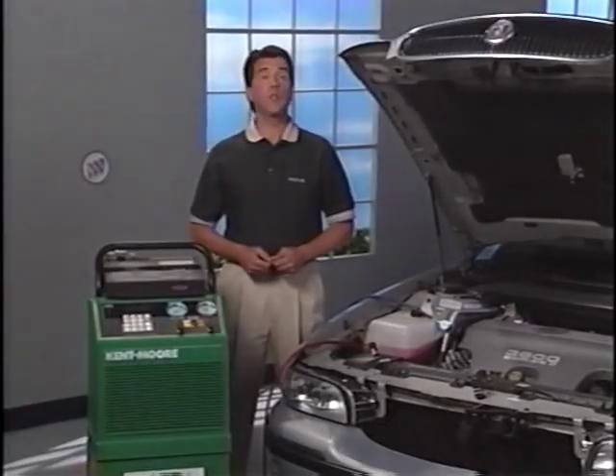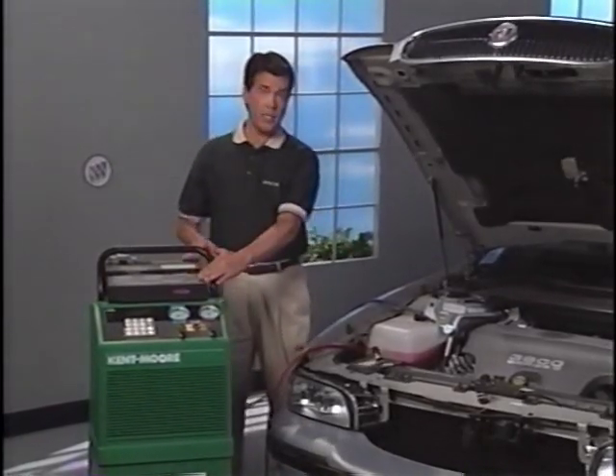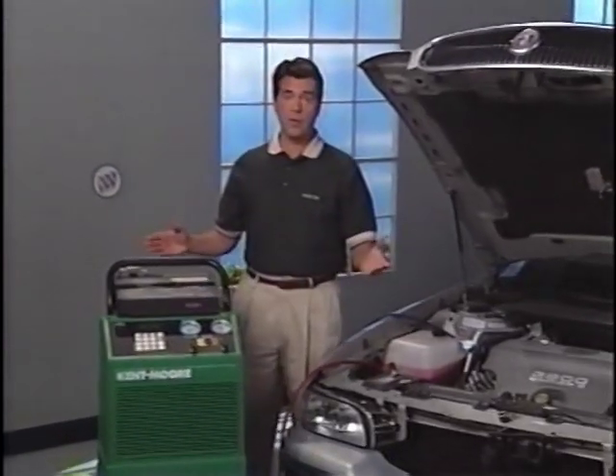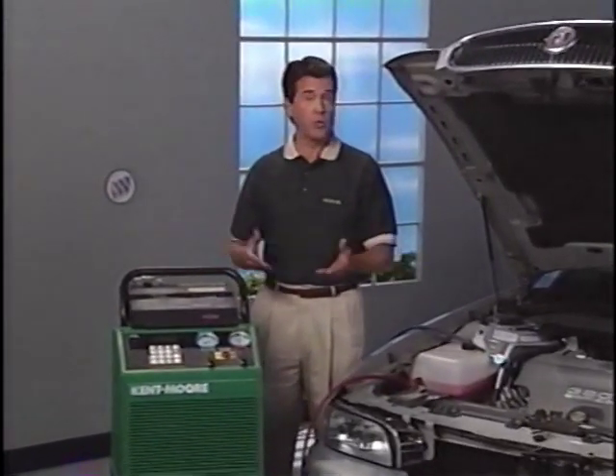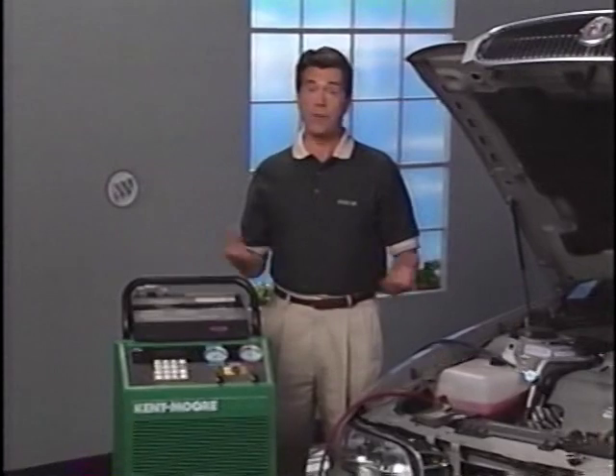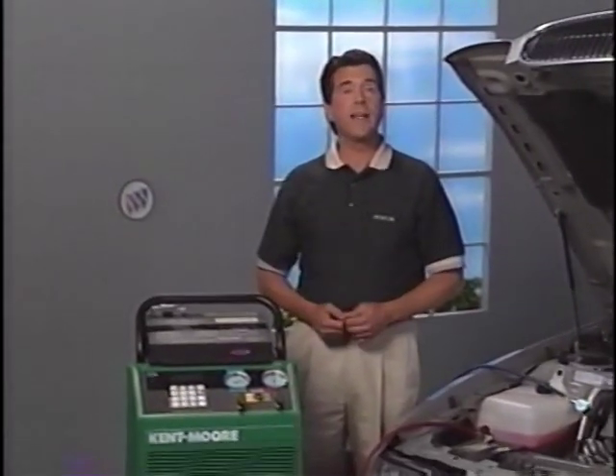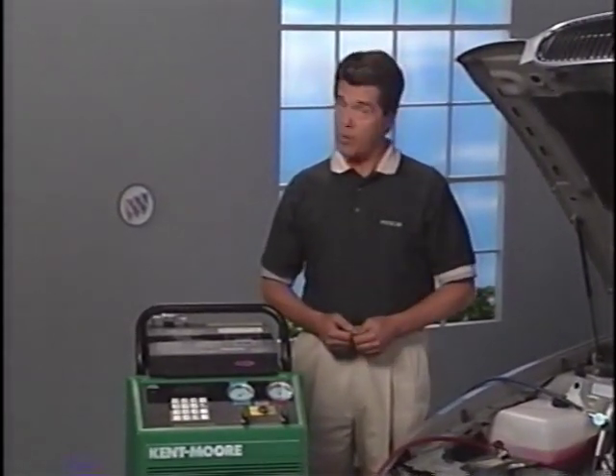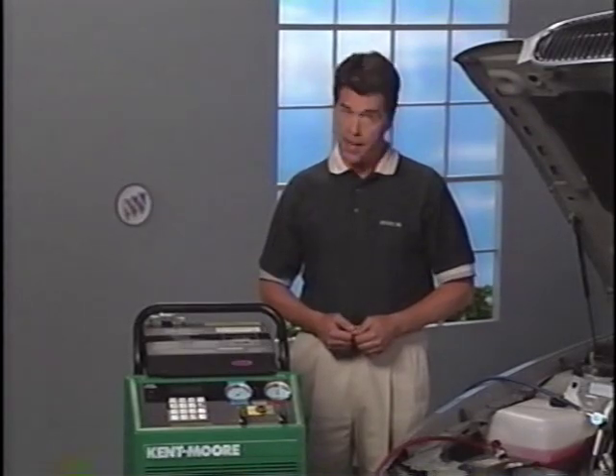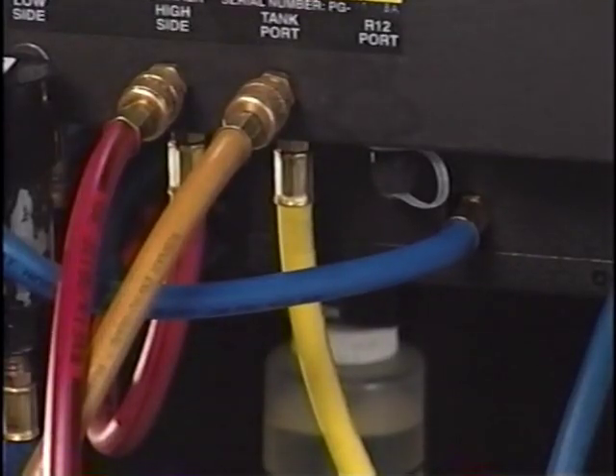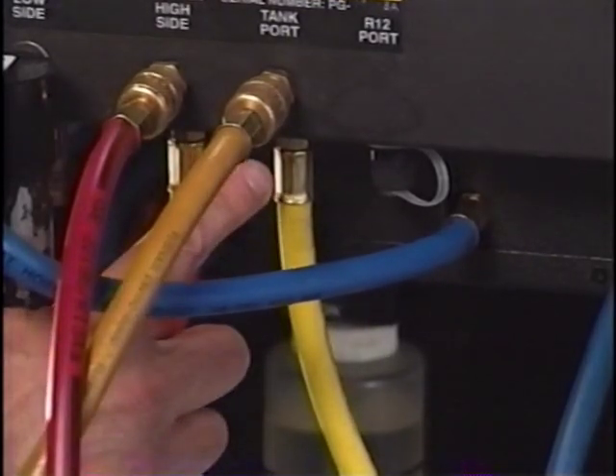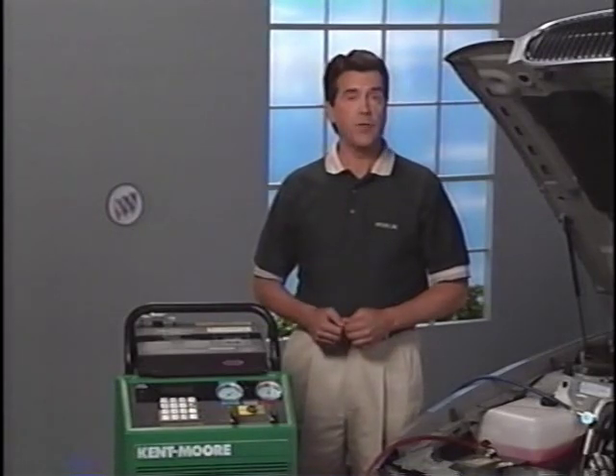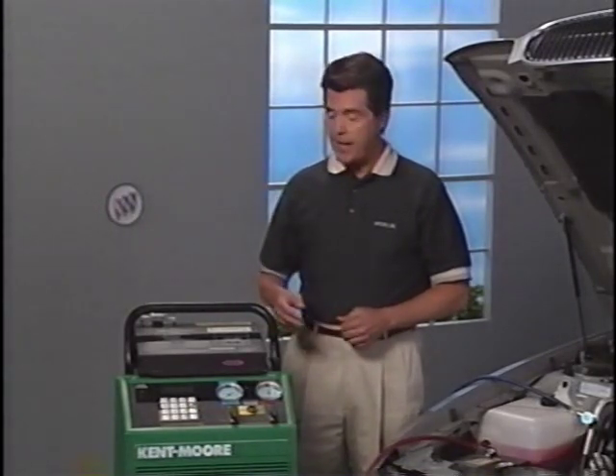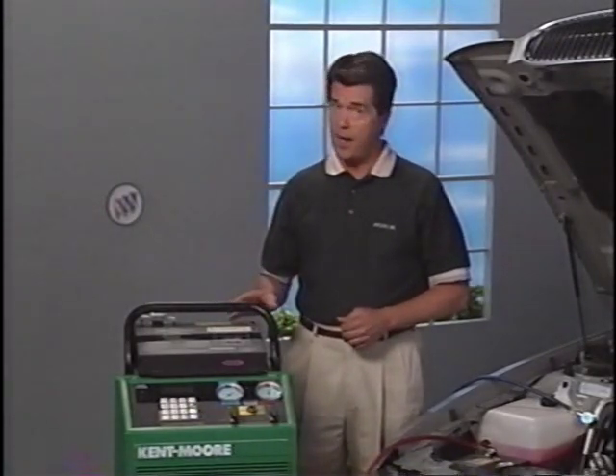As we saw, Bruce was using the PureGuard 2 unit on the ACR4, and although we turned the system on and off many times to shoot our video, it performed without any problems. The system takes only a short time to warm up and quickly reads the type of refrigerant it samples. Be sure the yellow hose from the PureGuard 2 is attached to the yellow fitting on the ACR4 and not to the tank. You may find the fuse blows in the PureGuard 2 when the ACR4 vacuum pump turns on.